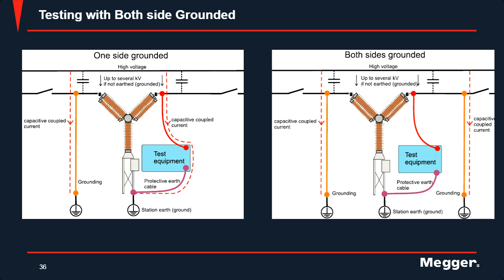So in most cases when you go to test a circuit breaker, you're already putting two grounds on. Most places require you to have a physical open disconnect and then two grounds, and then work between those two grounds. However, when you go to do conventional timing, you have to lift one of those grounds in order to do the timing, because you have to put a voltage on one of your test leads. And if it's still grounded, obviously it's just going to go to ground. So once you lift that grounded connection, your test set is going to be induced with the capacitive coupled current coming off any phases that are close to it and inducing onto your line. And if you don't have two grounds there, your test set is now that path to ground based off your instrument's ground lead.